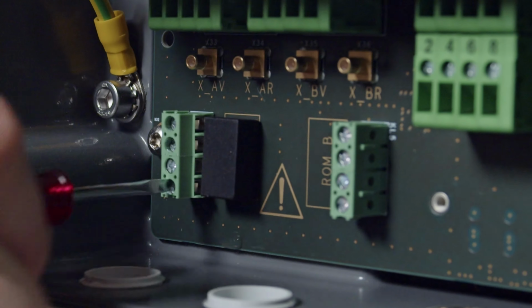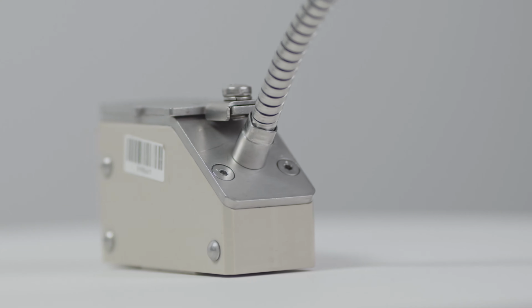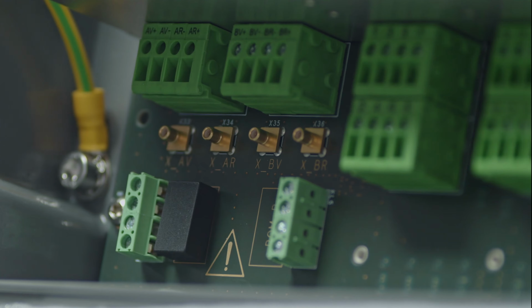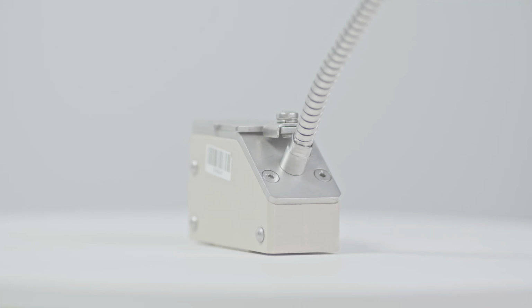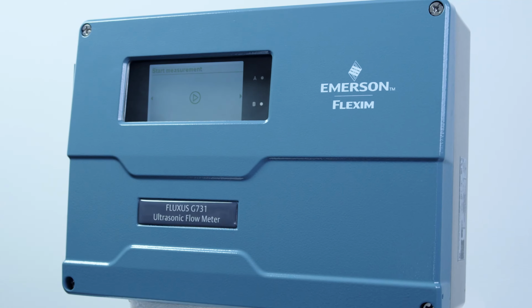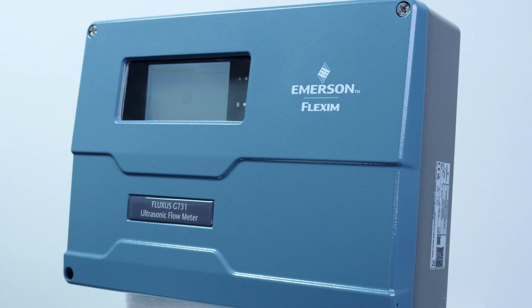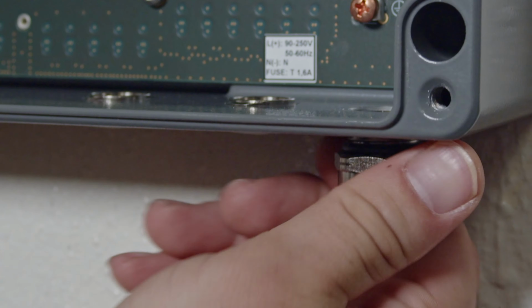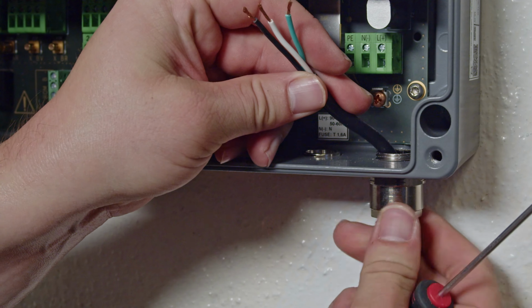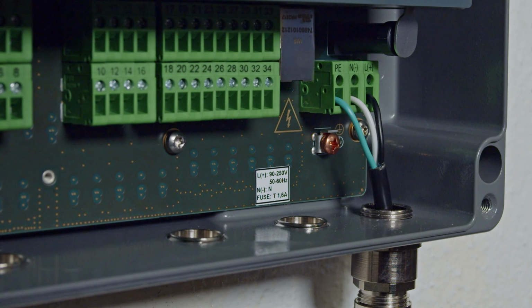Terminate the included SENSPROM chip into the highlighted terminals and connect the included flow transducers to the highlighted terminals. All sensor identification and calibration information will be automatically recognized once energized. Use the included conduit fittings to connect power and energize the equipment.